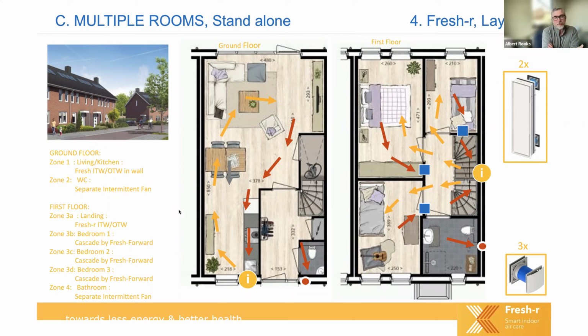A Fresh-Forward doesn't take air from that hallway or stairway area and push it into the bedroom. It does the reverse, which is super interesting. It actually depressurizes that room. On board, at the front of that little Fresh-Forward, is a CO2 sensor. So if nobody's in the room and there's no CO2 production, then it doesn't really need to do anything.